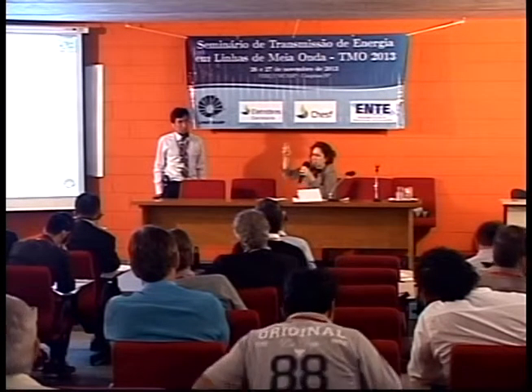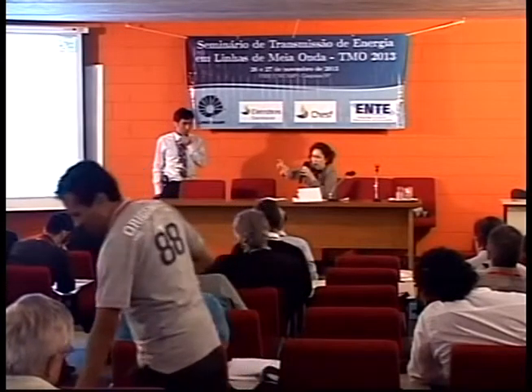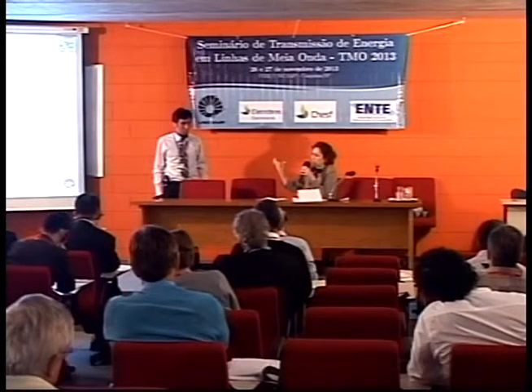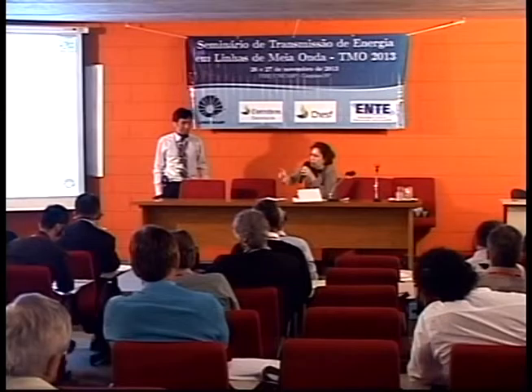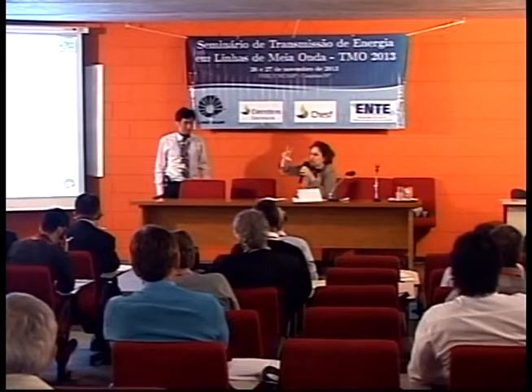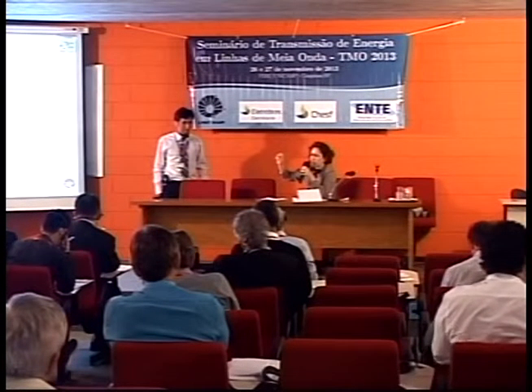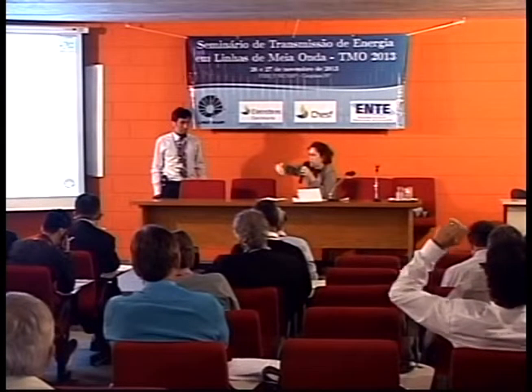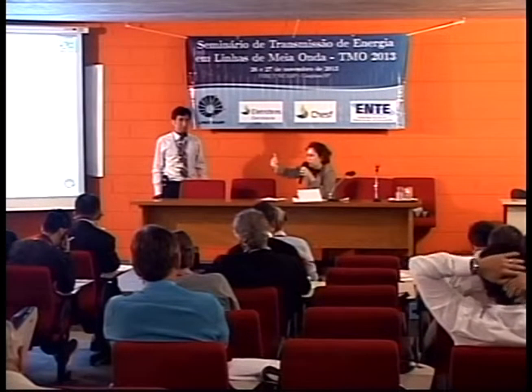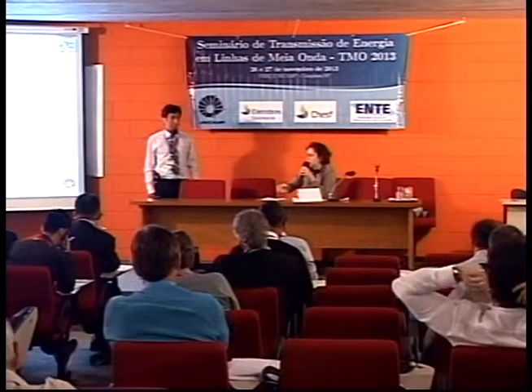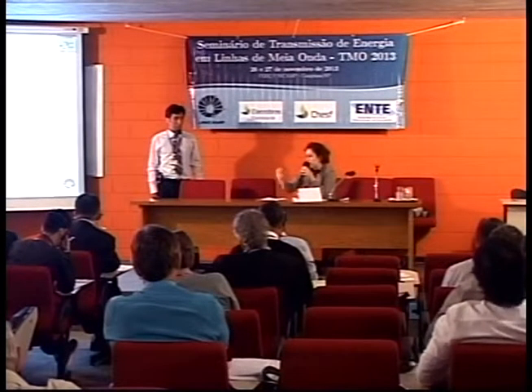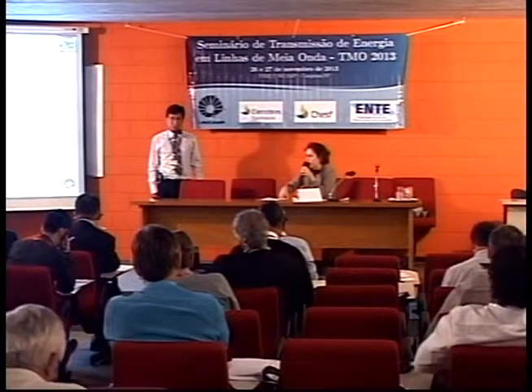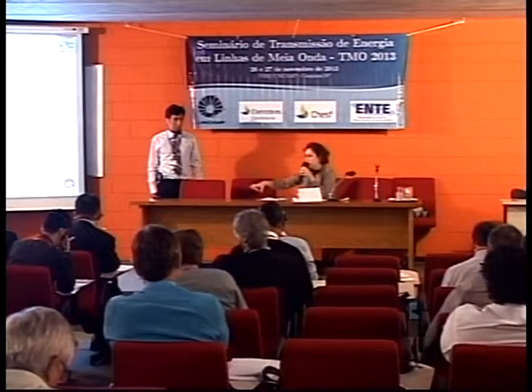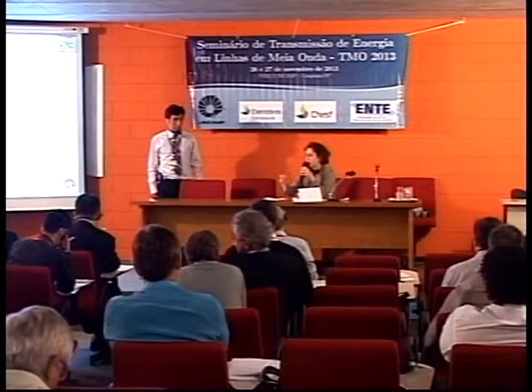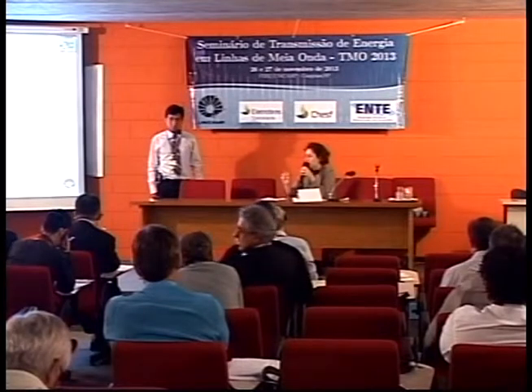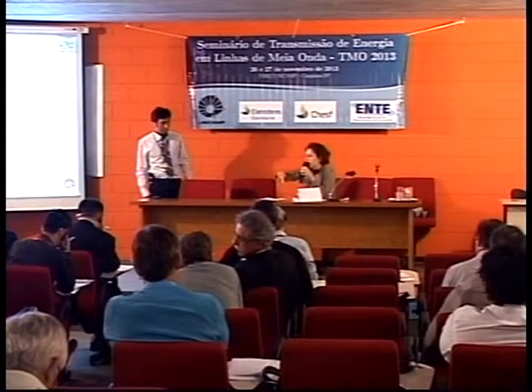What we are doing when we fragilize the isolation chain in Imperatriz, we are forcing this arc in a place that we know is proper. I'm not going to let the arc break anywhere. Because 4 pu, if you get an article saying the voltage will get to 4 pu, the person was lost in simulation. Simulation says 4 pu, but actually it doesn't get to that because it's going to break the arc before that. Where it breaks the arc, automatically removes it from the quasi-resonance situation.